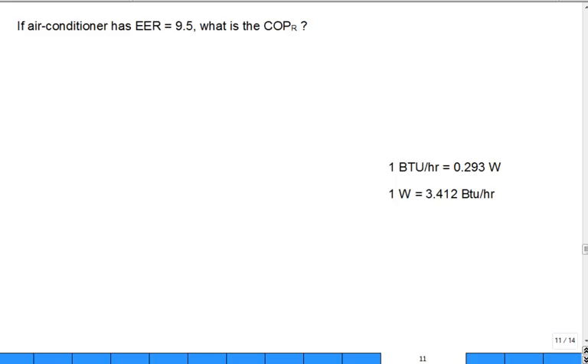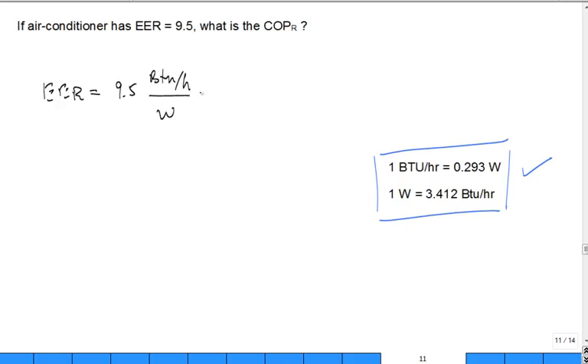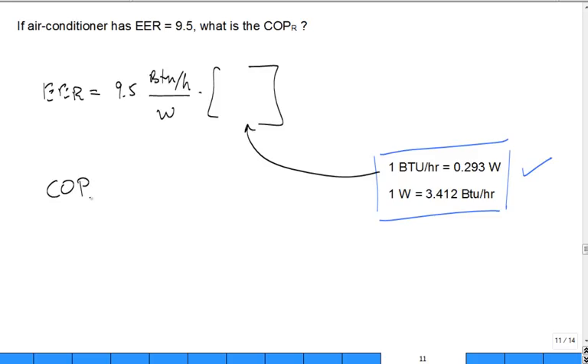If the air conditioner has an EER of 9.5, and yet in this class we studied COP for refrigeration cycles, can you convert the EER of 9.5 to an equivalent COP? You would probably need the unit conversion information to do it. To solve this problem, we write down what the EER is: 9.5, in BTU per hour divided by watts. All you have to do is multiply by a unit conversion factor to make it truly dimensionless, and it becomes the COP of the refrigeration — because the COP has the same definition: rate of cooling divided by work or power input. It's just that EER has it in cumbersome units.